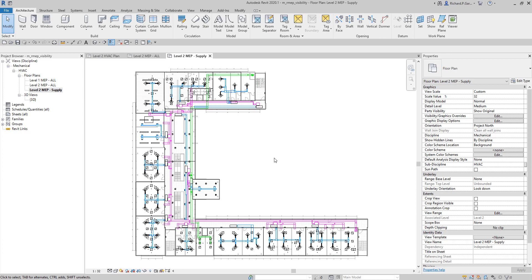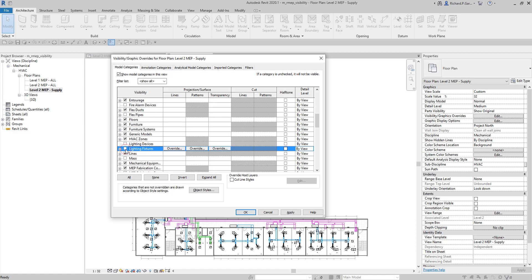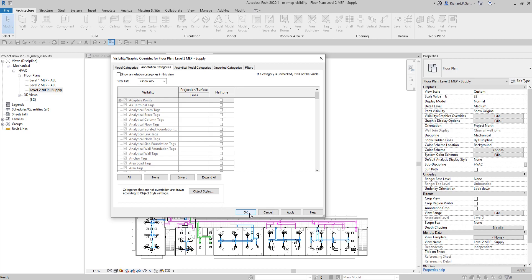Now we'll configure this new view. First, open Visibility Graphic Overrides and uncheck the lighting fixtures to turn them off. After that, we are going to turn off all annotations in this view. Instead of unchecking them one by one, just uncheck 'Show Annotation Categories in this View' - this will hide all annotations including tags, dimensions, elevation symbols, and section symbols.